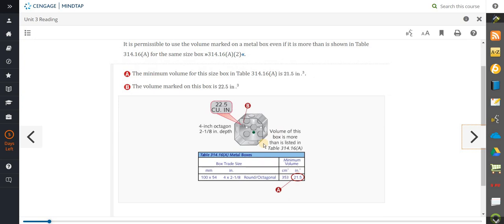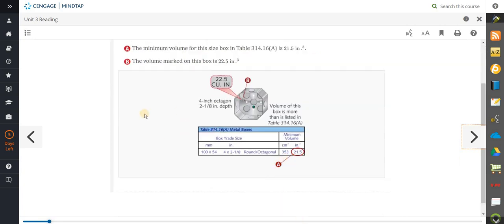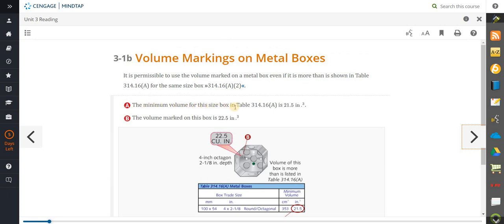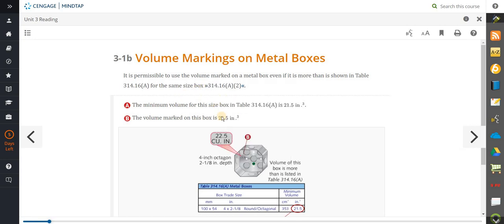Here's an example — it's talking about the cubic inch volume of a box, and to help you out, every graphic has what's called an identifier. So it's talking about A — A goes right here. In this case, 21.5 is dealing with the question: that's the minimum volume for this size box per table 314.16a, which is 21.5 cubic inches. Anytime you see code references like this between these arrows or brackets, you want to look them up in your code book. You always want to read the material, have your code book with you, and look up the code sections.